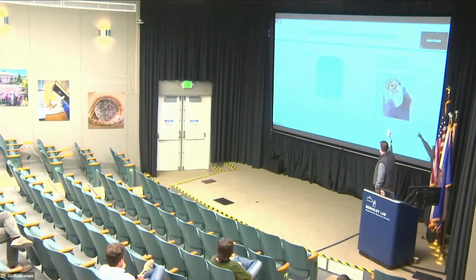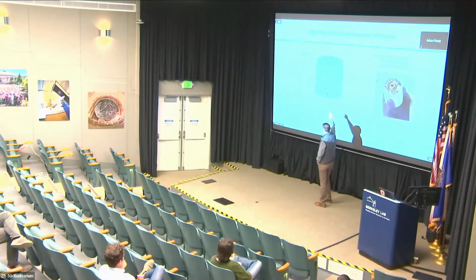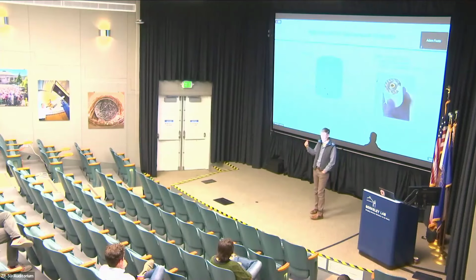So this is what a germanium crystal looks like. This is the heart of our detector. It's just a cylinder of very pure germanium. And when a gamma ray interacts in this germanium, we've configured it to act like a semiconductor diode, and we have about 1,000 volts. Actually, for a space instrument, we go up to about 3,000 volts.